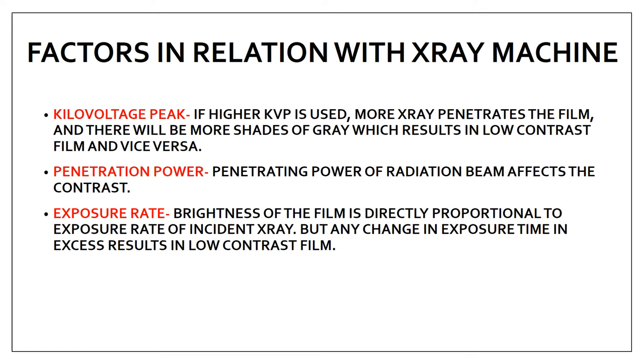The next are the factors in relation with the x-ray machine. We have a control panel with different parameters, and changes in those parameters can affect the contrast of the film. The first is kilovoltage peak (kVp): if kVp is high, the contrast of the film will be low — it is inversely proportional. If a higher kVp is used, more x-rays penetrate the film and you will have more shades of gray, which is a low contrast film. If kVp is low, contrast will be high.